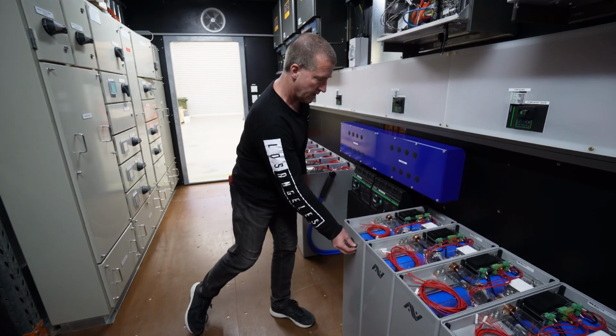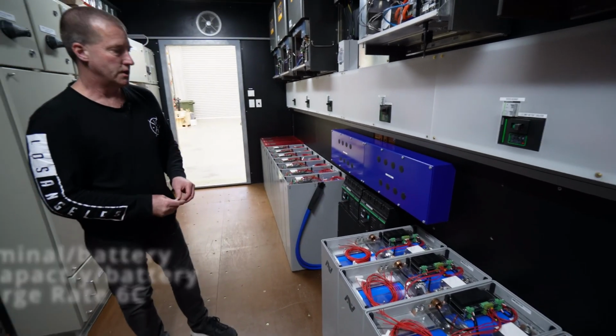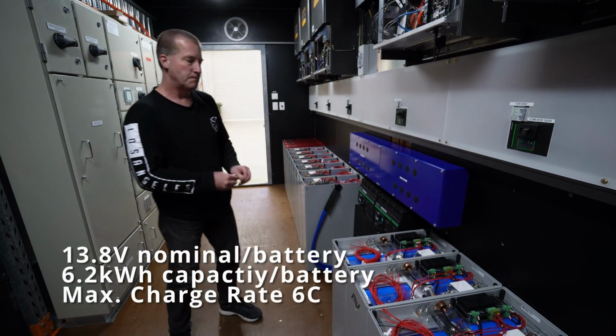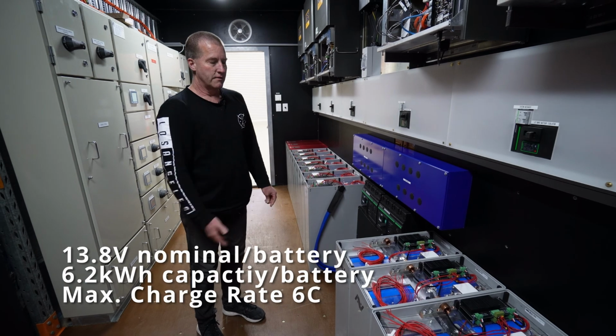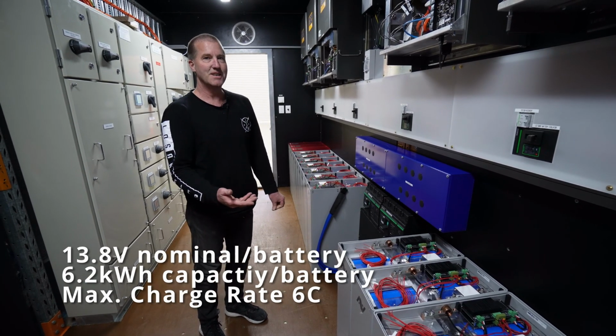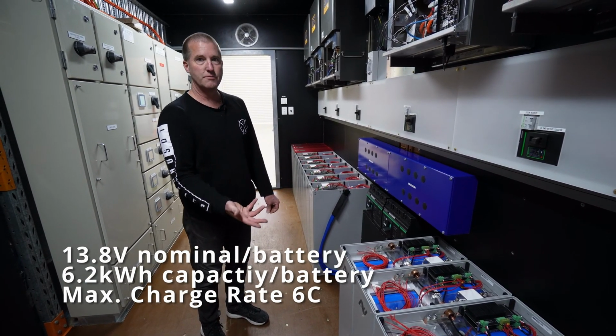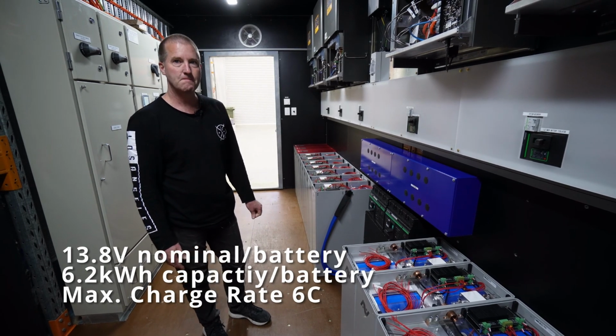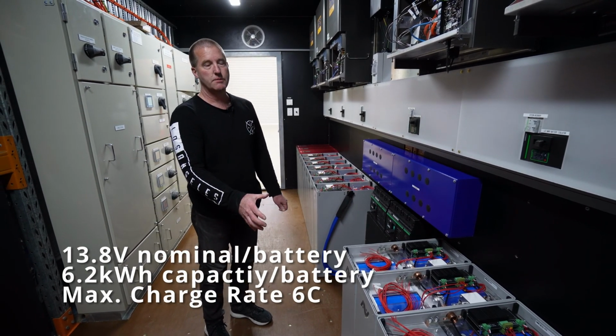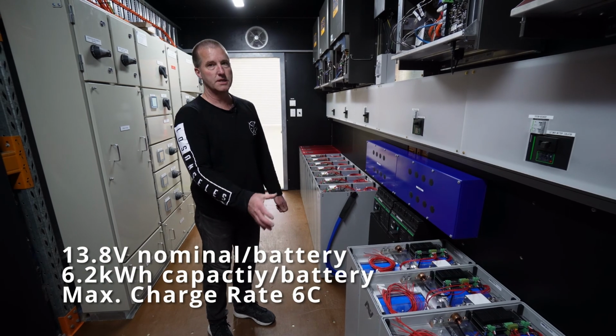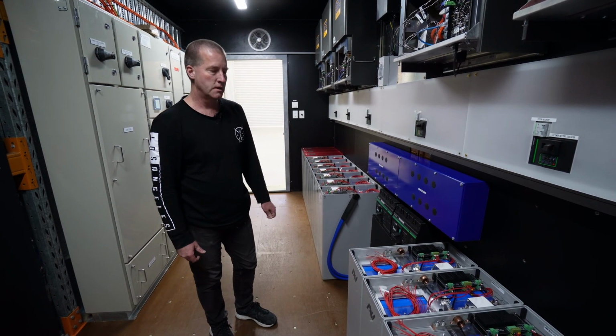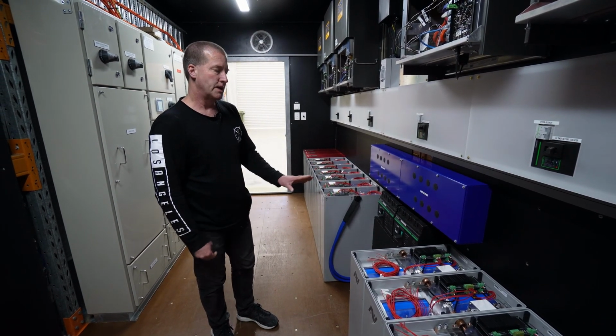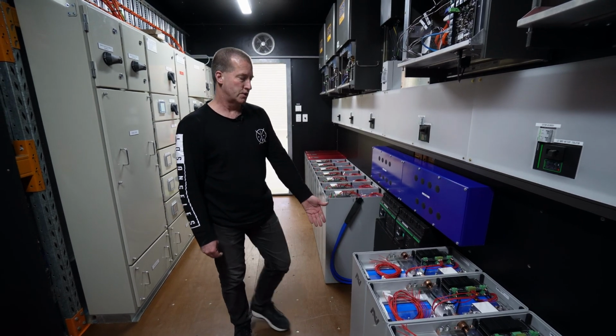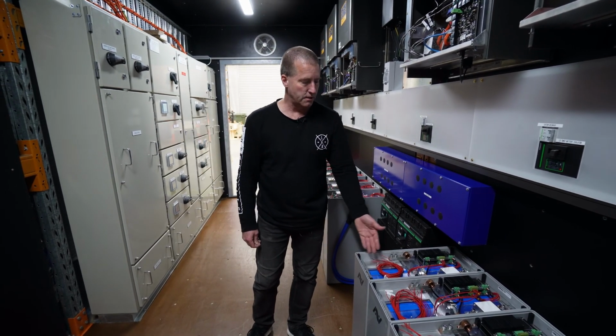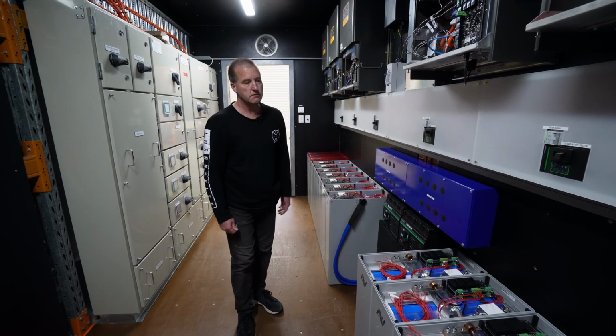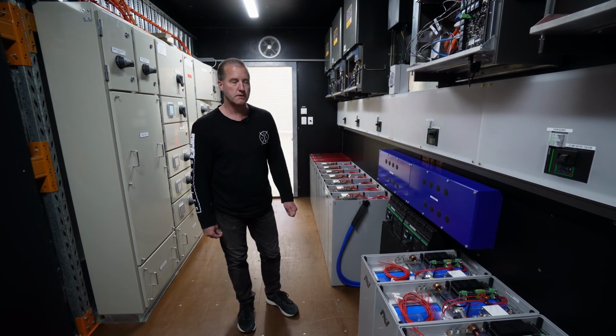Basically each module here is 6.2 kilowatt hours of storage, with a C rating of 6C, so it can charge up in 12 minutes. 6C? Yeah, you can charge it 6 times the C rating continuously. Wow. But you can charge faster if you want - up to 10C, just for shorter periods of time, and discharge as well. Another thing to be careful of is heat, caused by internal resistance of the copper, aluminium and the cells. As long as you deal with heat, you can charge at really any rate you can imagine.